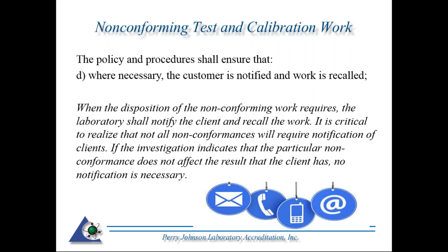Okay, the policy and procedure shall ensure that D, where necessary, the customer is notified and work is recalled. Hence, we did our investigation. We pinpointed customers that it actually impacted, they need to be notified, and if needed, the work recalled. So when the disposition of nonconforming work requires, the laboratory shall notify the client and recall the work. However, it is critical to realize that not all nonconformances will require notification of the client.